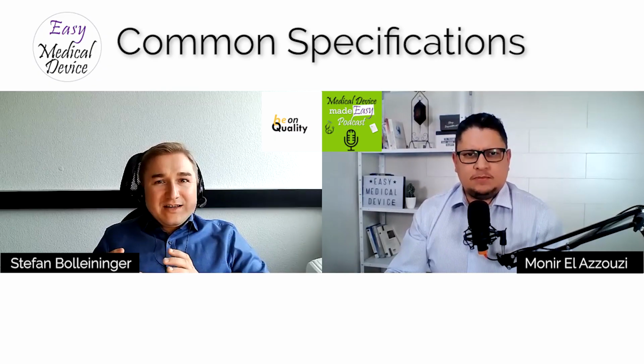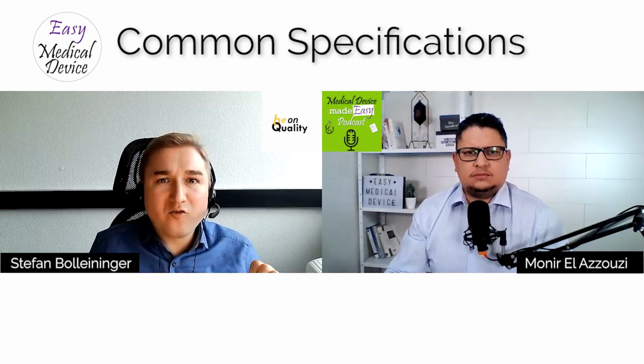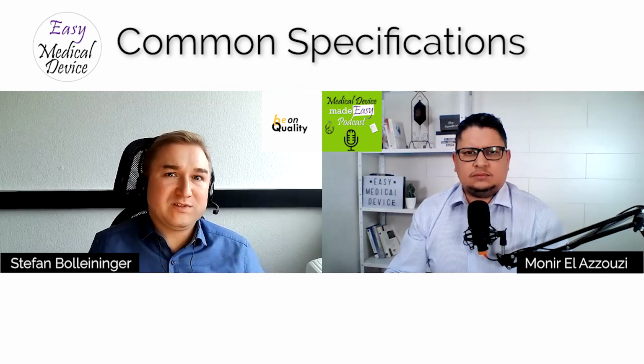It's half and half, and that's a funny thing. For example, if you're an Annex 16 device, a device without medical purpose, then the common specification is the law. In case you have a product and you have sufficient standards and all of that, then you can say you have a common specification in addition. So in this case, it's not that much the law as for the Annex 16 devices. It's a bit schizophrenic, but we need to live with it. And my perspective is to always take a common specification as the law, except if you have a very good opinion why you do not need to do that.